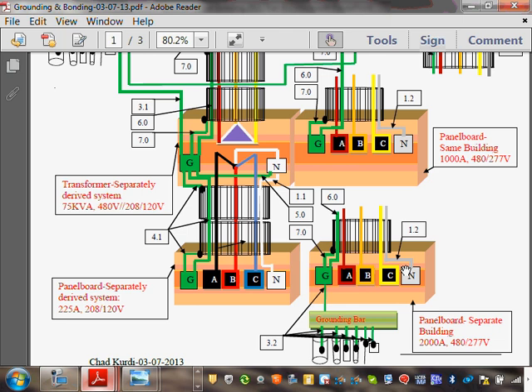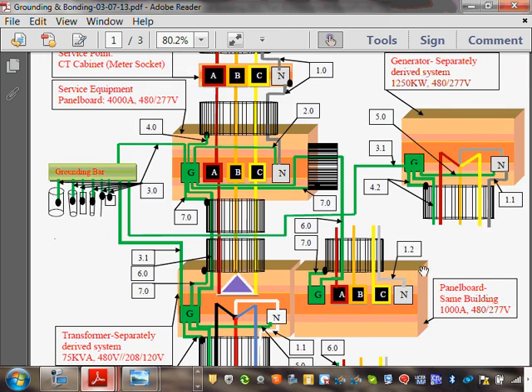Now to spice it up, you can't have a system without a generator, right? So I threw a 1250 kW generator right next to your hospital or sport arena or your house. And for that 1250 kW, 480/277, we need to do grounding and bonding, and tie this generator to the switch here. I know some of you guys are journeymen. I hope that the larger amps, the larger kW and the larger voltage do not scare some of you, especially the green ones.